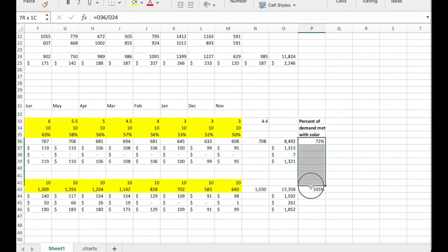Now, these are two estimates, 70% and 100%. I was aiming for a production of about 80% of our demand. So I'm feeling pretty comfortable with the 10 kilowatt sizing, and this is how you can play around with different sizing for your array by using these numbers and looking at the results of how much demand you're meeting based on current results and PV Watts estimates.